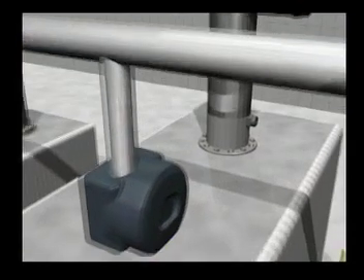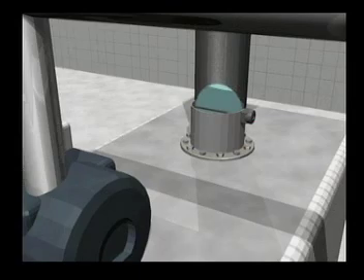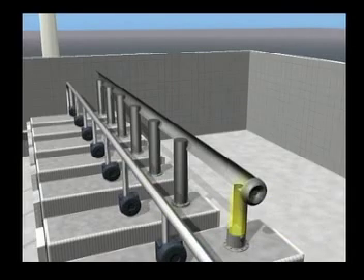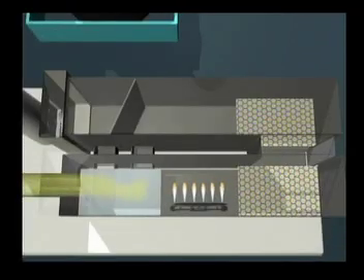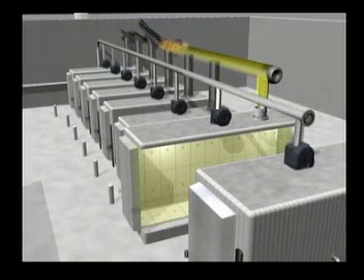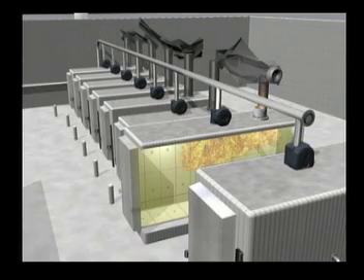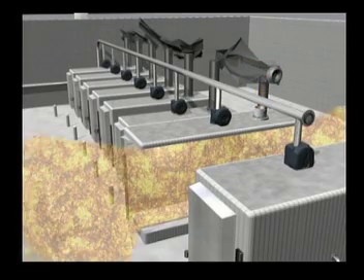A short time later, the front door was raised, activating the chamber ventilation system. This drew a large amount of ethylene oxide from the chamber through the back vent to the open flames in the oxidizer. The explosive gas ignited. A flame front traveled back through the ducting into the sterilization chamber, igniting the remaining ethylene oxide and causing a powerful explosion.